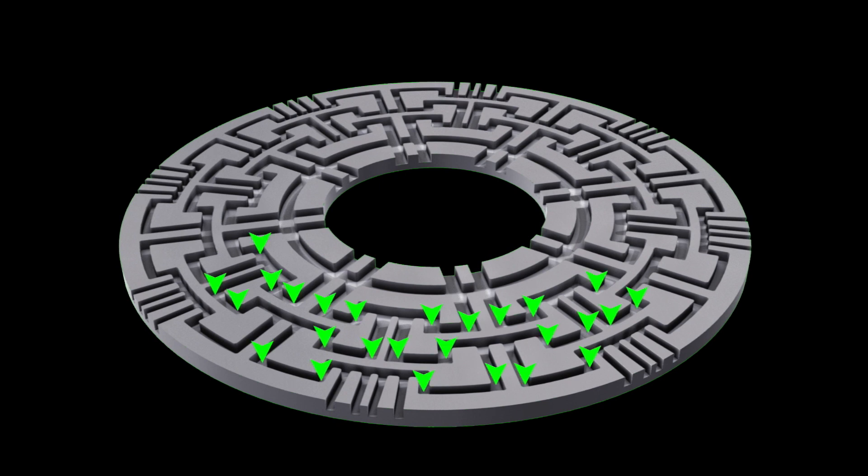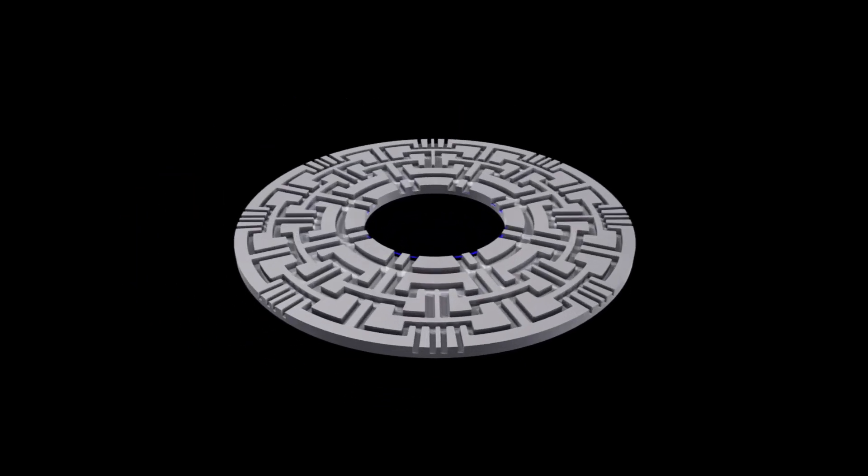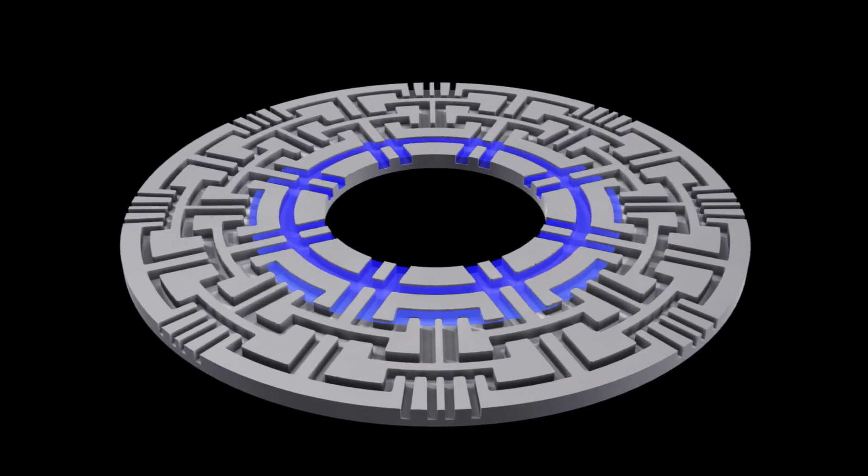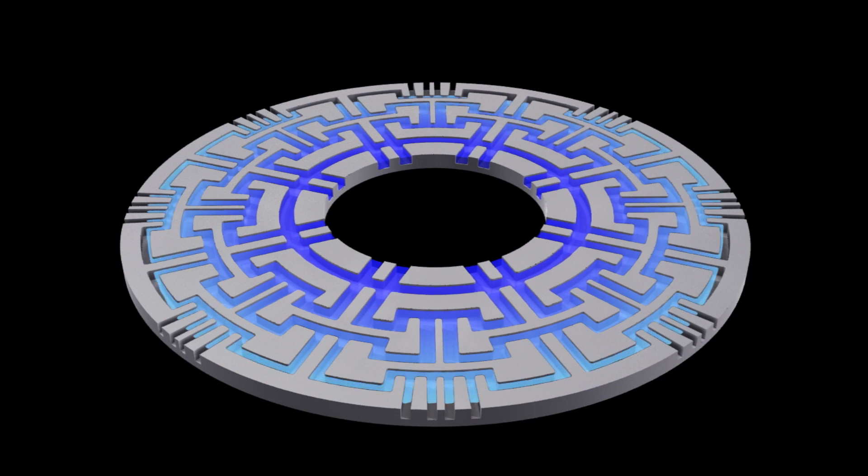Each sharp turn provides a single-stage pressure drop, which are arranged in series to properly control fluid flow. The fluid enters the inlet of the valve and turns through the numerous flow paths until it reaches the outlet at a greatly decreased noise and velocity.